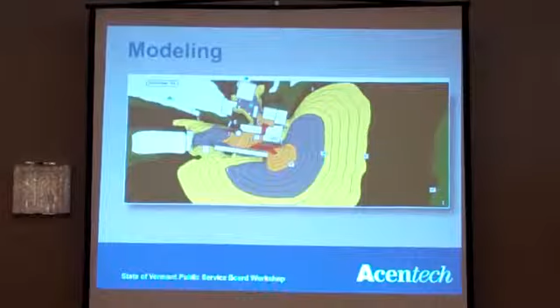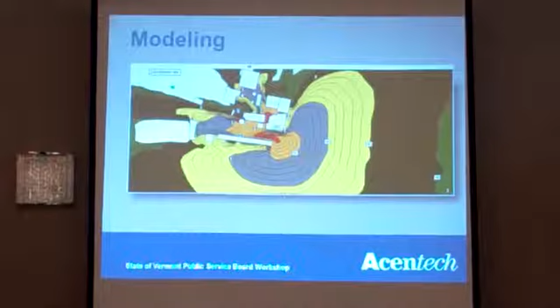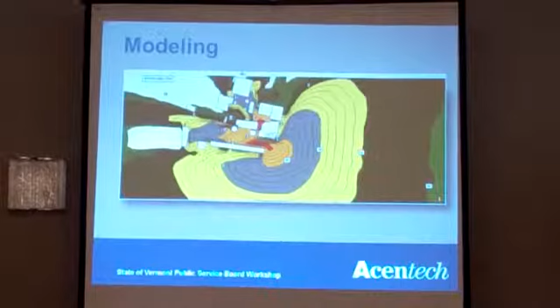As part of the overall permitting with the state agency, they also decided to put in an air-cooled condenser unit, something needed to remove the waste heat from this process, particularly the newer process which generates a lot more waste heat. In the past, they used to take that waste heat and dump it into a river reservoir, but they were concerned about the increase in the thermal load in the river.